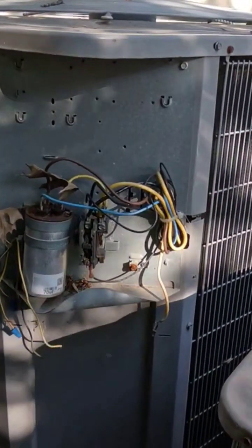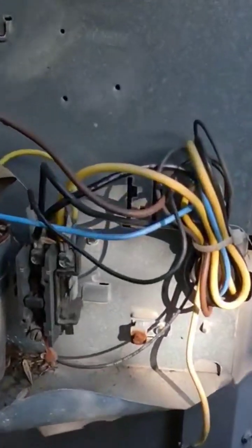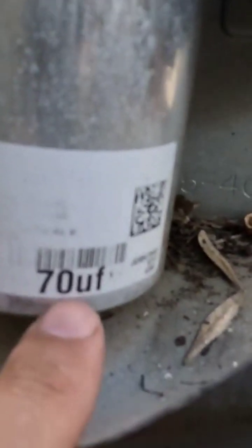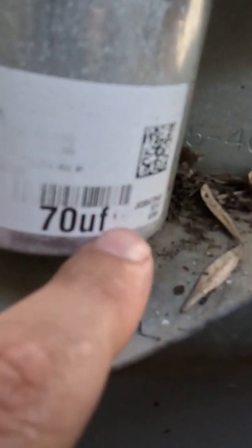We're going to talk about what size capacitor you need for your HVAC system. Looking at this dual capacitor here, a lot of the label is missing. What we do know is that this capacitor is 70 microfarads — that's the rating for your compressor. But then there's another smaller number for your fan, and we don't know what it is.